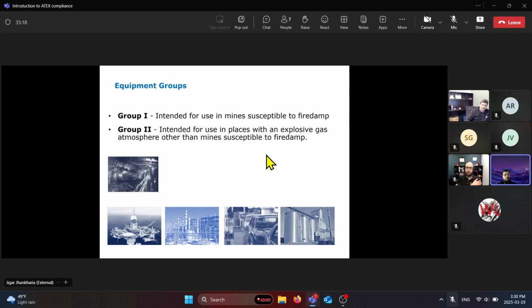Group 1 equipment usually is only used in mines. Group 2 equipment is more common, which is used in an explosive gas environment other than mines. So most of your tools would be in Group 2 equipment classification because it's not being used in mines. Unless you do get into the mining sector, then that method of protection will change.